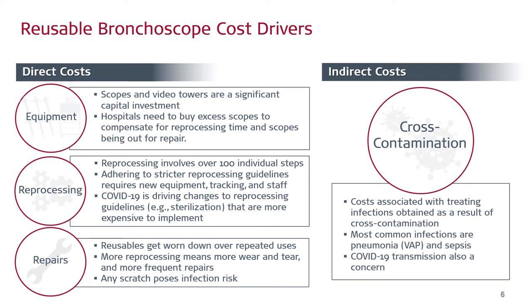Any scratch on a reusable bronchoscope poses an infection risk. If there's a scratch on the scope, bacteria and biofilm can get into that scratch and may not be captured or disinfected in the reprocessing cycle. So scratches and other issues with bronchoscopes need to be addressed.